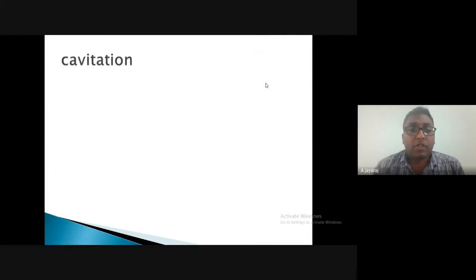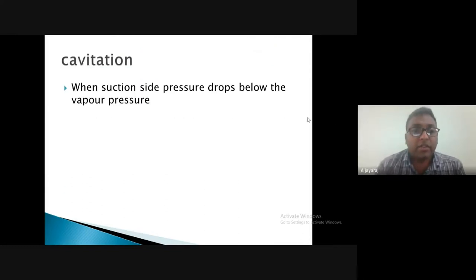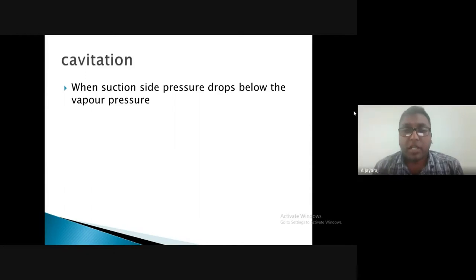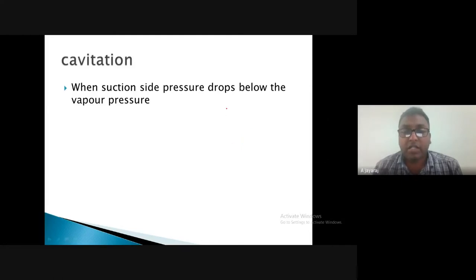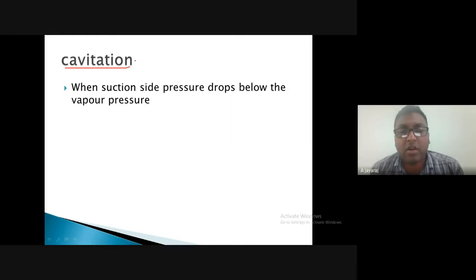Cavitation is a phenomenon that occurs on the suction side when the pressure drops below the vapor pressure of the liquid. When suction-side pressure drops below vapor pressure, a problem called cavitation occurs — involving formation of cavities on the blades or inner surface of the casing.